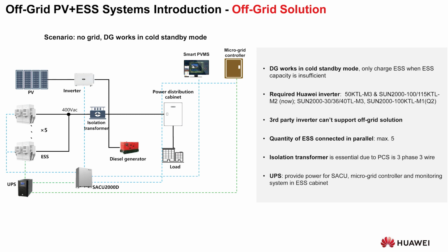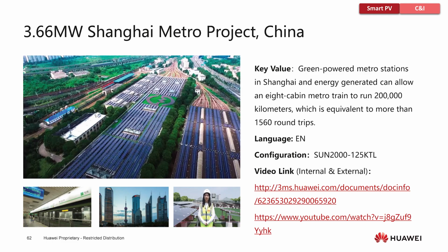Okay, off-grid solution where the DG is the main power. So there's no grid, ESS and DG as the main power. You can see here, you're still going to put 5 together, your PV, your inverter, and your diesel generator is connected on this part of the line, okay? You've got your power distribution facility here, your loads are here, your microgrid controller is here, and you need a UPS. I'll send you all this so you can have a look at all these diagrams and how it is connected, okay? So this is now a microgrid solution.